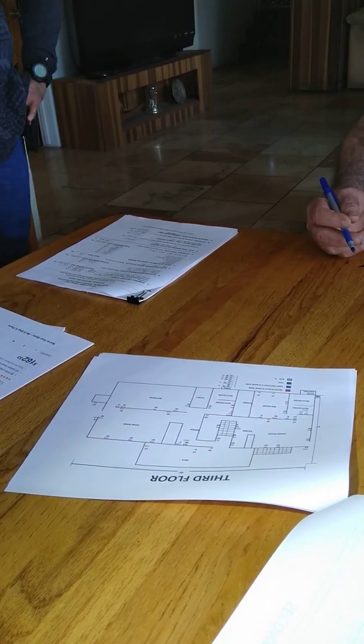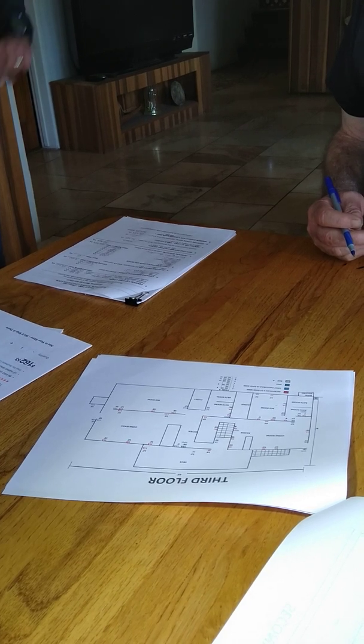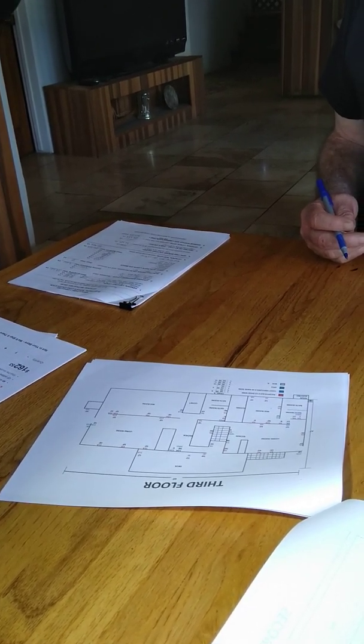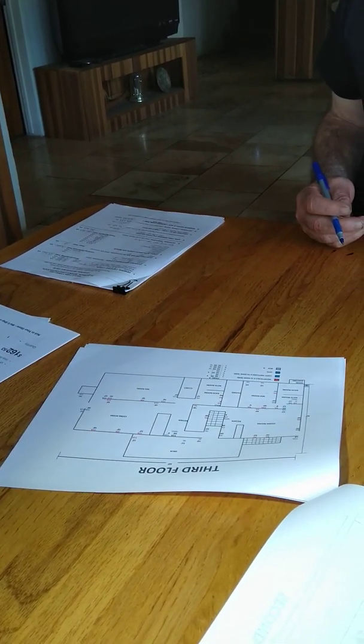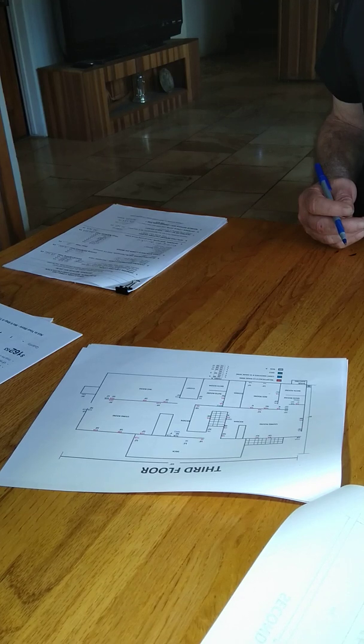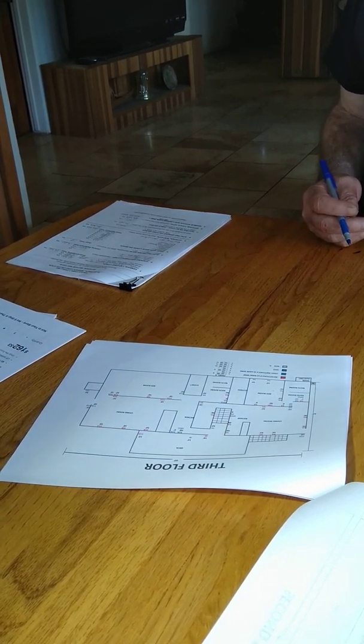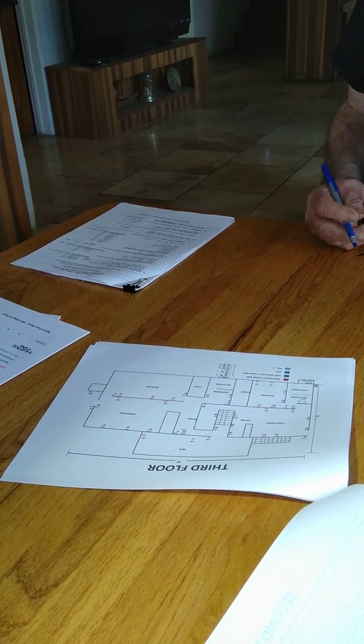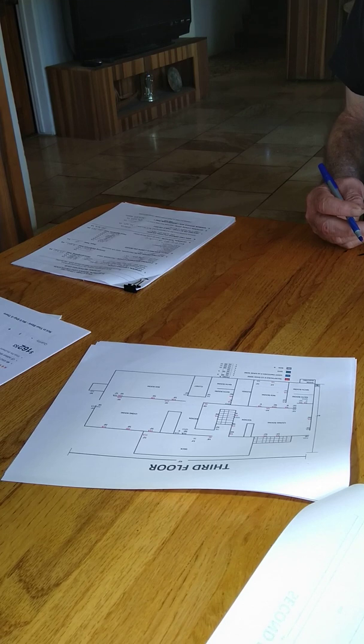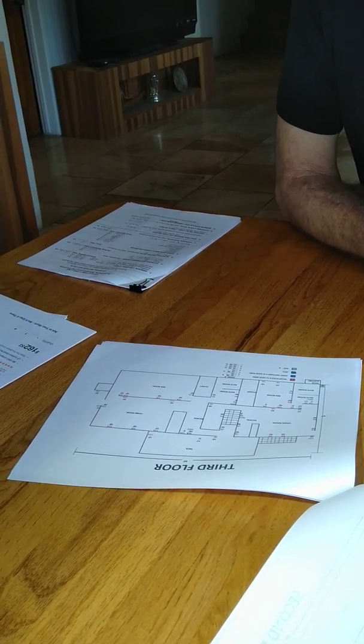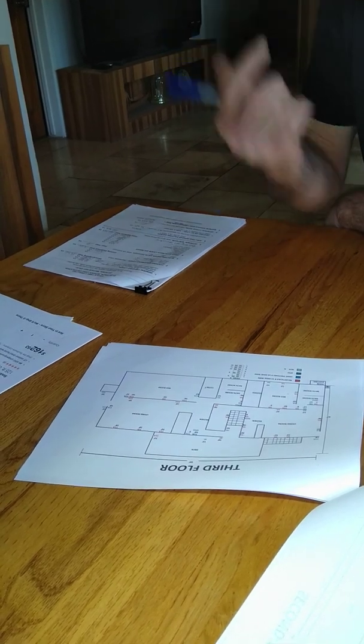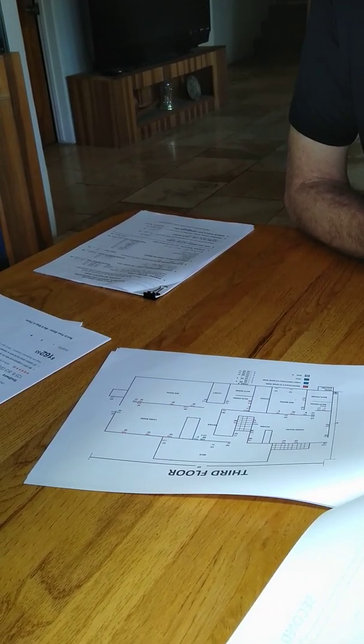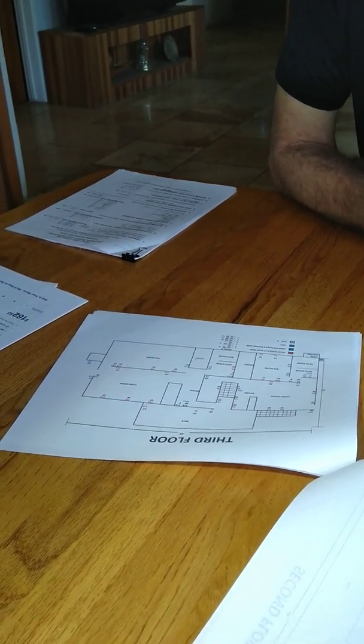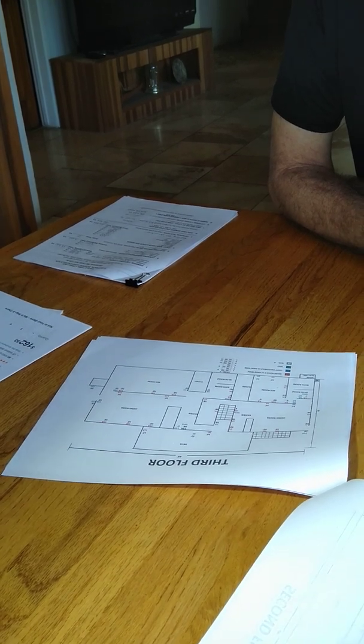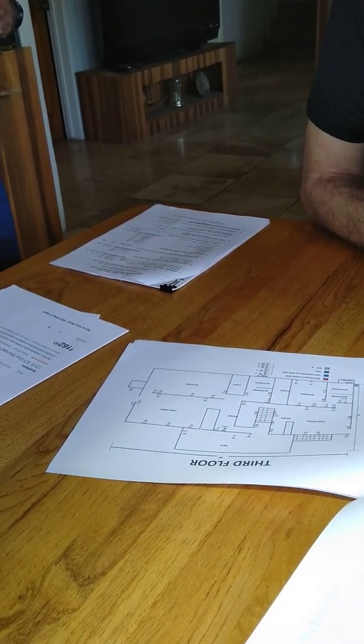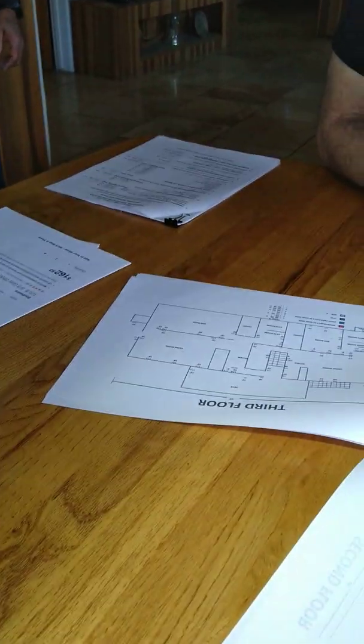Okay, so here's where we go with that. We have to figure out what size circuit breaker is required. And then based off of that, that'll give us a size of what the conductor needs to be. Then we think about the distance, because you're going to have amperage start to decrease because of the length. So it's called derating. I'm just going to use this as an illustration. Let's say it's a 20 amp circuit breaker. Typically you would only need a number 12 gauge to supply that, but because of the length, you would have to increase the size of the conductor. So for argument's sake, if you had a number 8, it would work because of the length. So you upsize the conductor to allow for the decrease in the run.